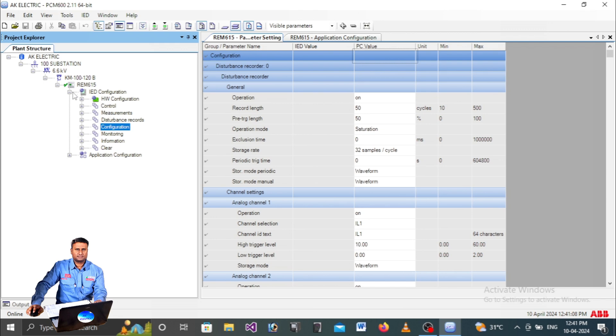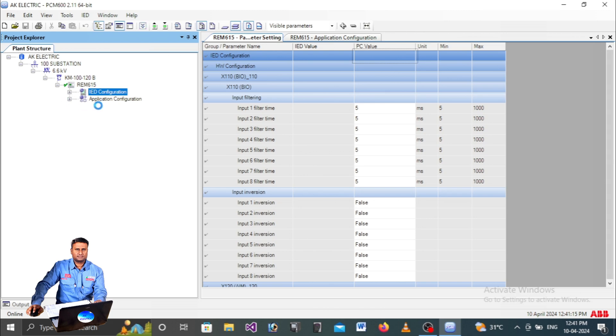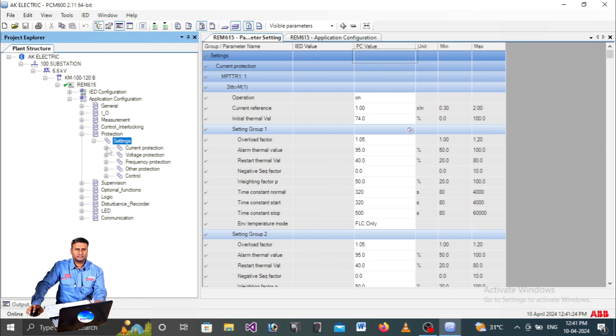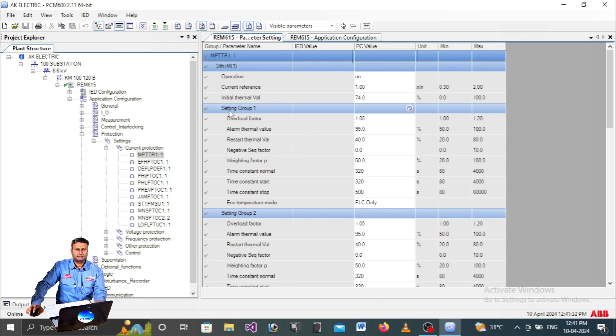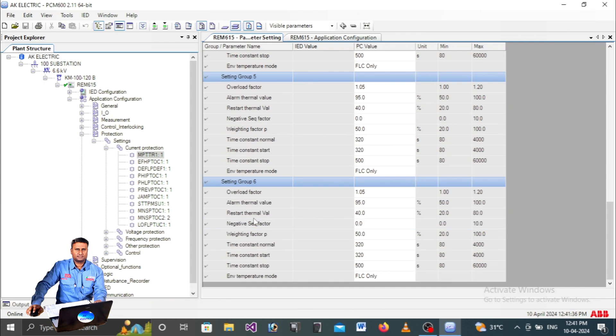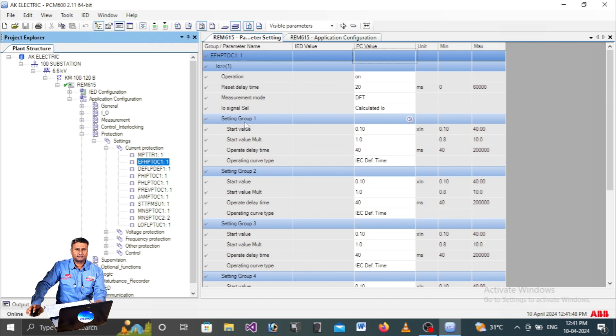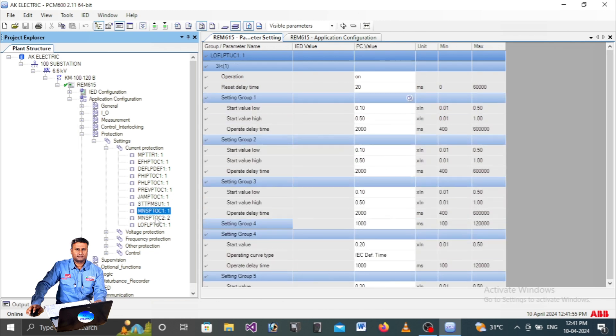We have only downloaded the default settings so far. We have not yet read the actual settings from the relay. Under Application Configuration you will find protection functions including current protections and voltage protections. Right-click and go to Parameter Settings, where you will find Group 1, Group 2, Group 3, Group 4 settings. You only need to check Group 1, as that is the active settings group.